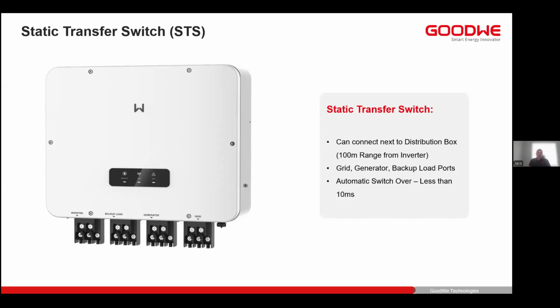So one of the big benefits of the STS is the fact that it can be connected to the inverter up to 100 meters away from the inverter. So in that sense, the STS can be installed closer to the main grid input, or the grid incomer, or if there's an existing generator, it can be installed directly by the generator, which will then maximize cable efficiency. The other benefit is that the heavy switching and the relays are installed in the STS. And typically, if there are major AC faults, those components tend to fail first. And in this case, the inverter is then protected from that.